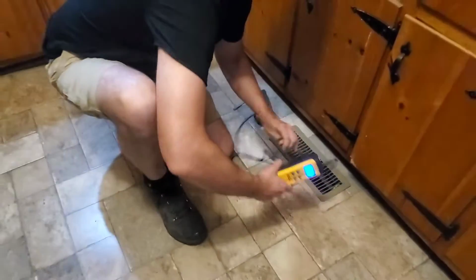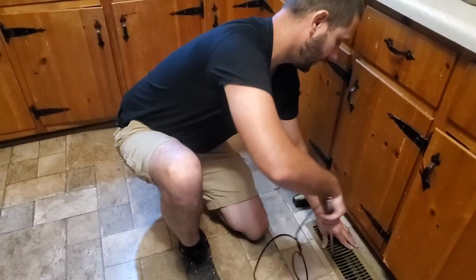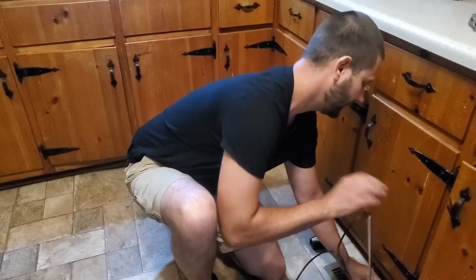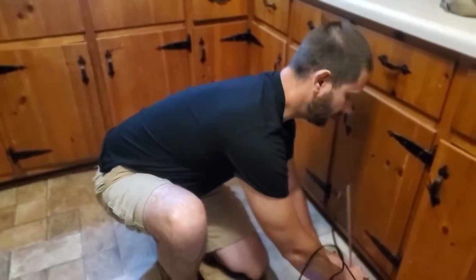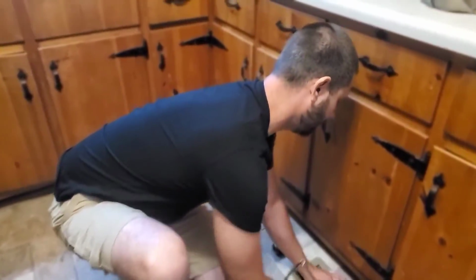We could actually speed this fan up and get more airflow, sacrificing a little of that temperature. So we just finished checking with our first tool, the temperature probe in the supply vent, and we can see our unit is performing the way it needs to - it has a 20 degree split or more, so we're in great shape.